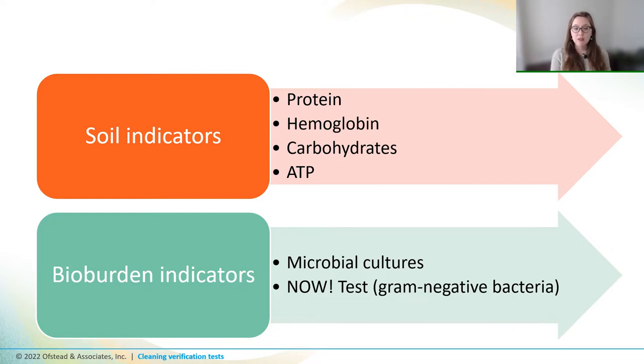For today, we're going to focus on the soil indicators, because cleaning is supposed to get rid of the soil before HLD or sterilization to help them work better. And tests for bio-burden come a little bit later in the process.